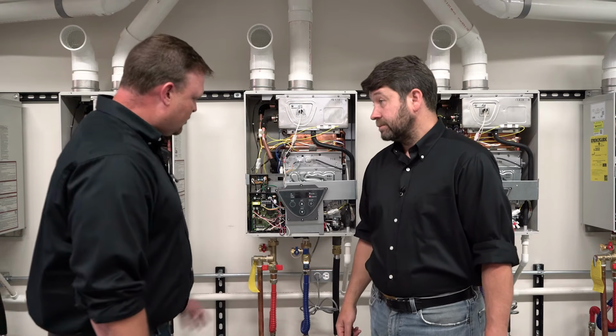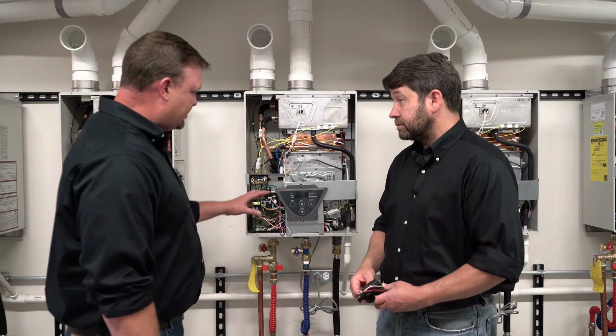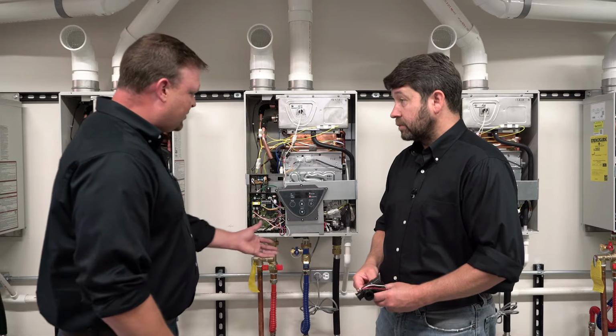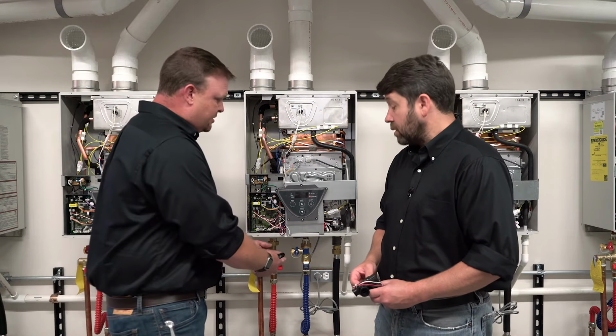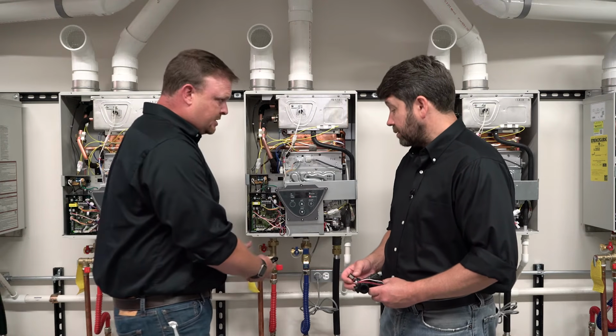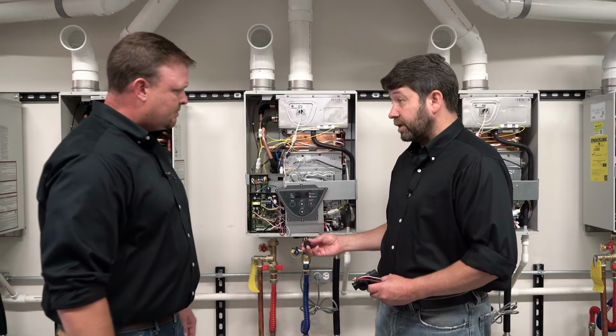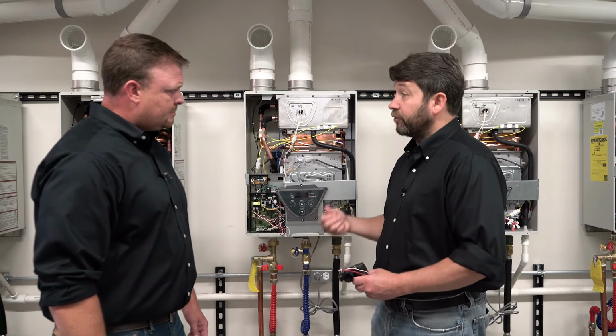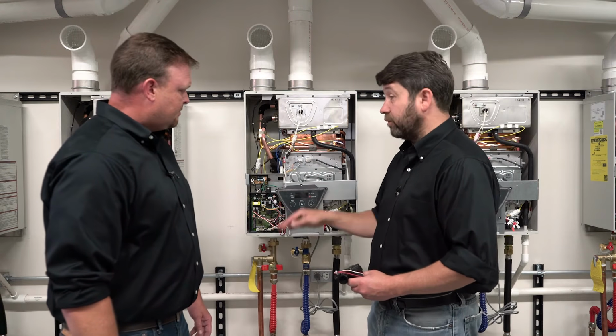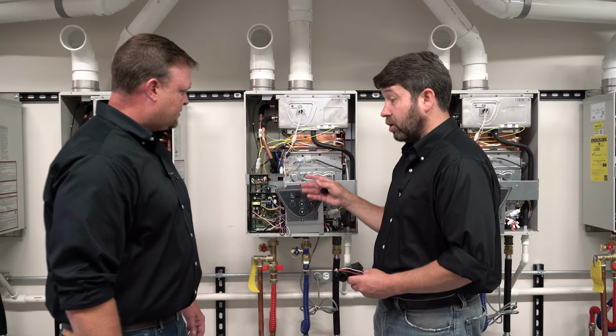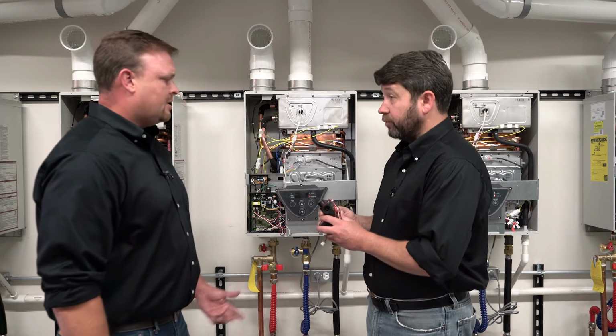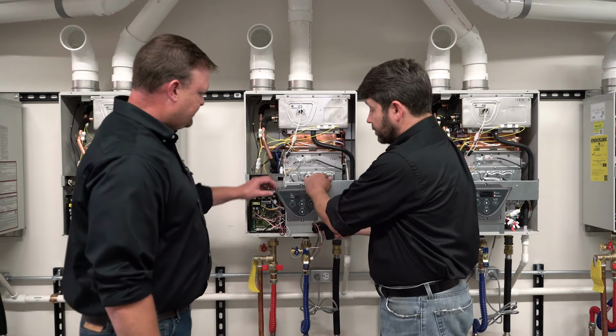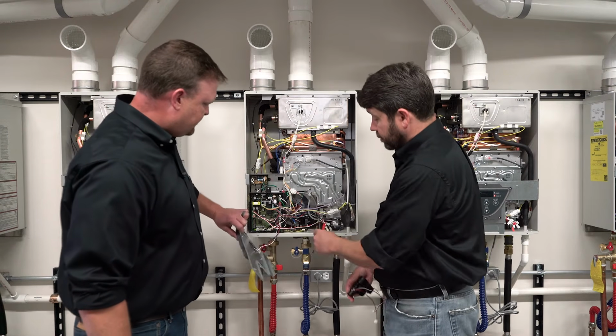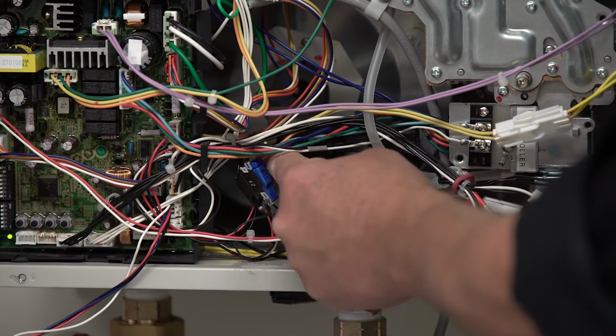Okay. All right, so once we've done that, is there anything else we need to think about when we're getting no hot water? I mean, is it going to be one or the other, or a cross connection? Well, that or cross connection. Once we get this cleaned out and put back in, if we're still having the same problem, we're still getting flow through the heater but it's not coming on, then we're looking at our flow sensor itself. The flow sensor is located right behind this user interface module, and there are two clamps that hold it in place.